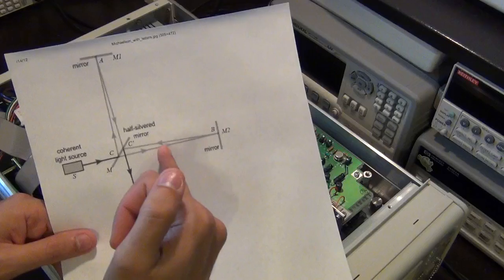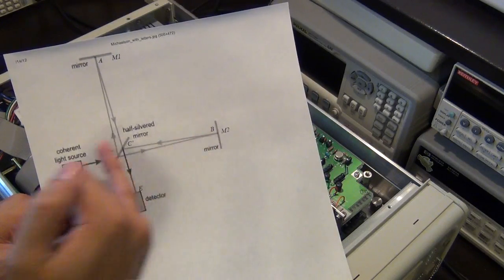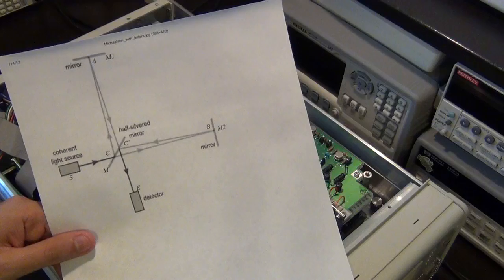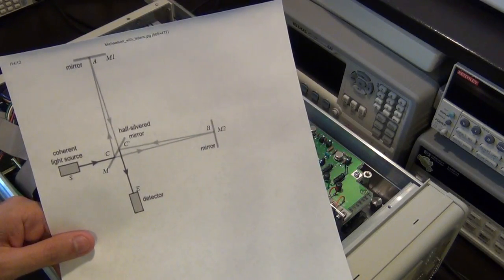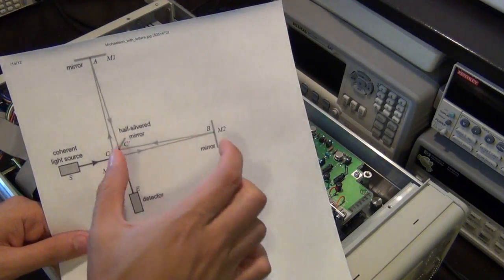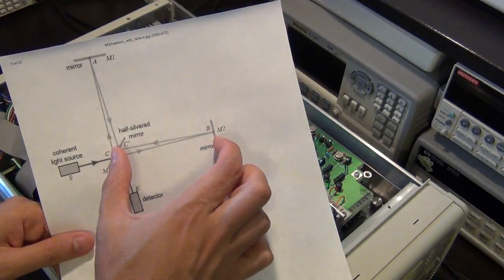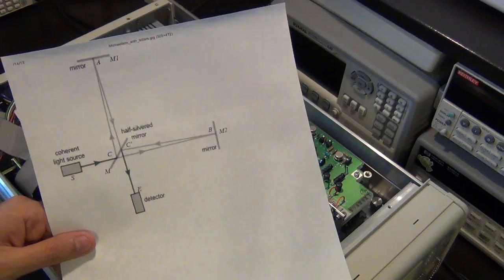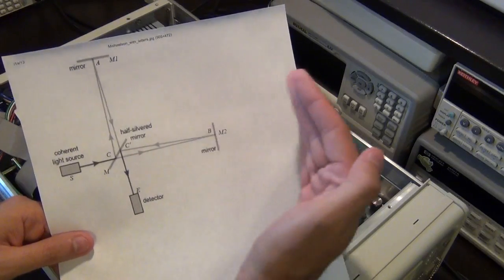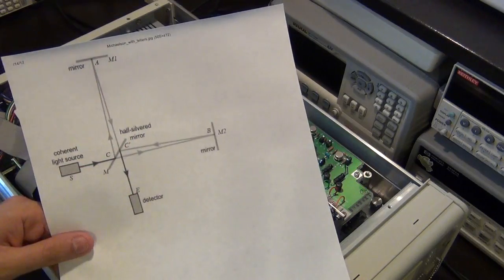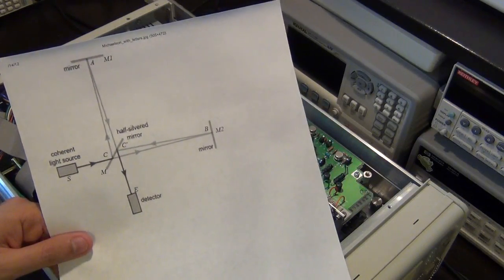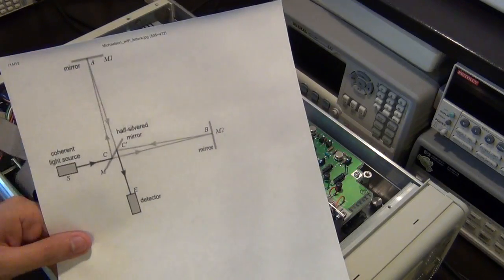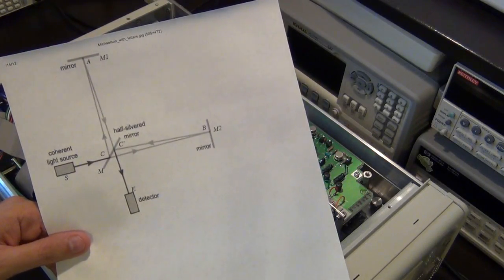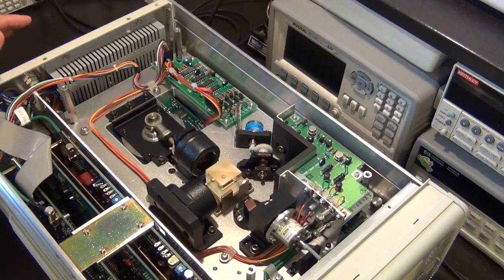So if I were to be moving this mirror back and forth, and I didn't know what the wavelength of this light source was, if I had a proper detector, I could measure the fringing pattern, and if I know the distance, if this is fixed and I know this distance, then I can measure the wavelength, which is exactly how this instrument works. It moves a mirror back and forth, and by shining this light through two mirrors, it can then measure the wavelength, because it has multiple detectors and it can measure the fringing pattern. This is a very simple explanation of how a Michelson interferometer actually works. But this instrument does all of that using free space optics.